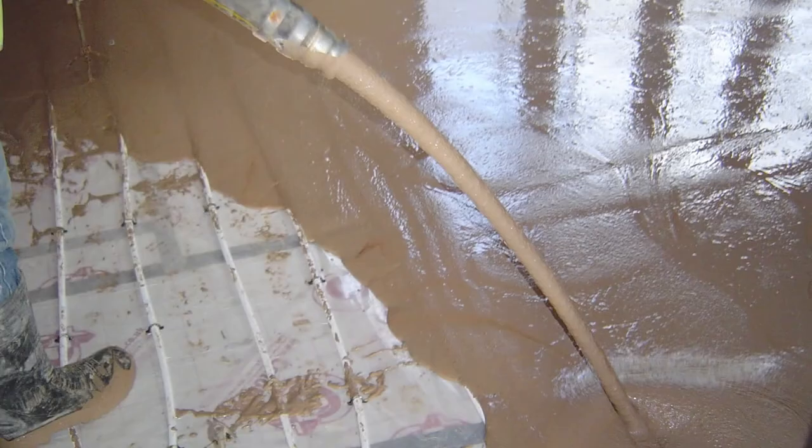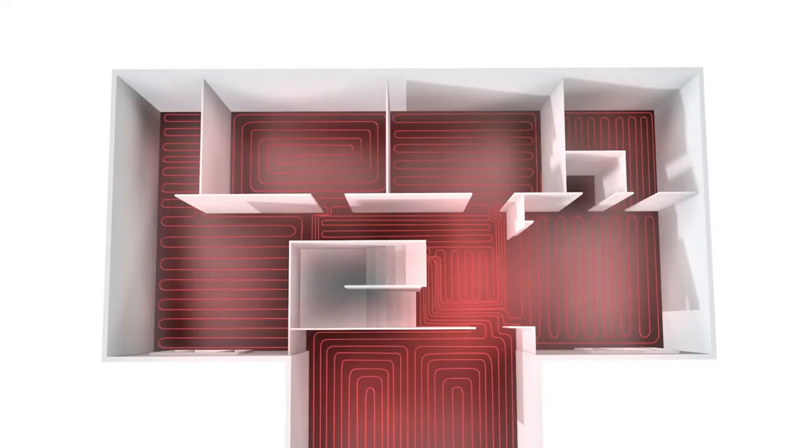However, calcium sulphate screeds may need only 7 days after laying. Check with the manufacturer for specific drying times. Under no circumstances should the UFH be used for speeding up the drying period.